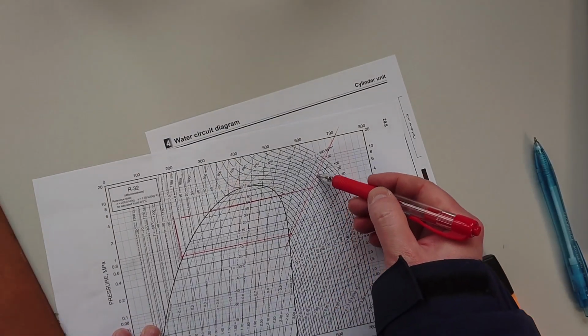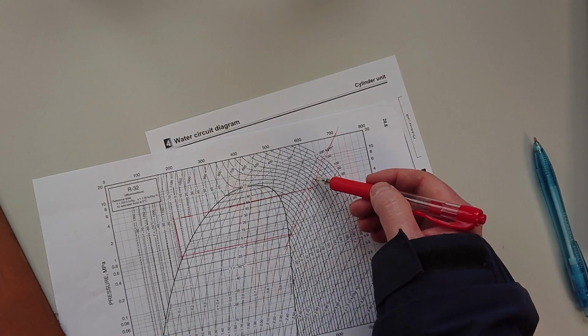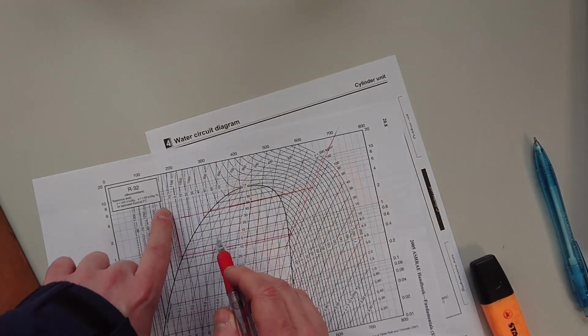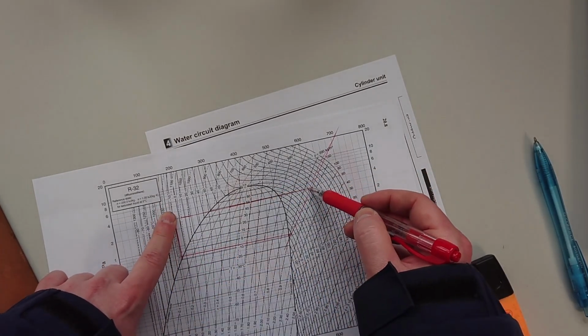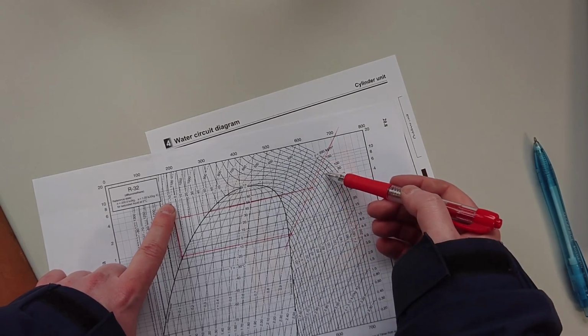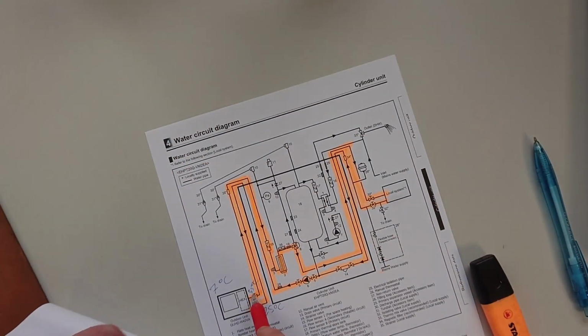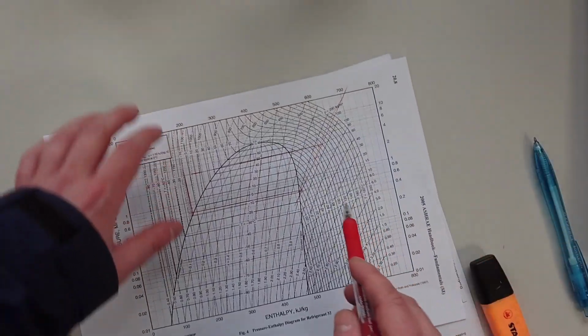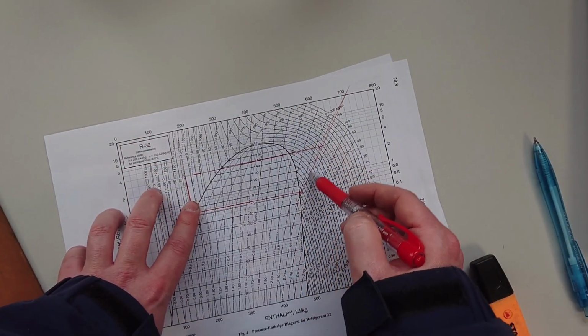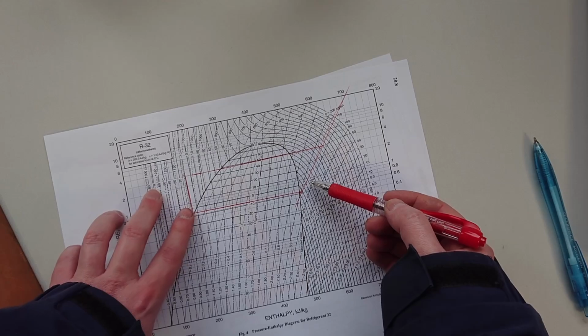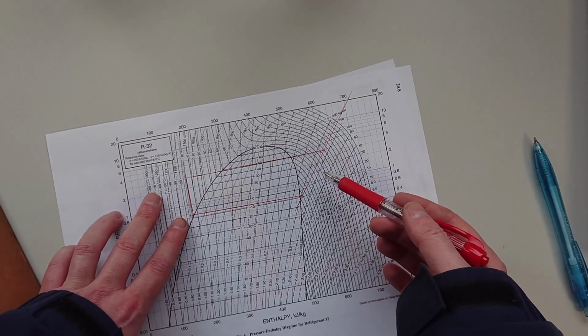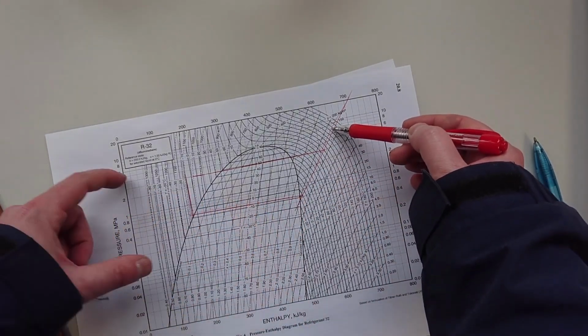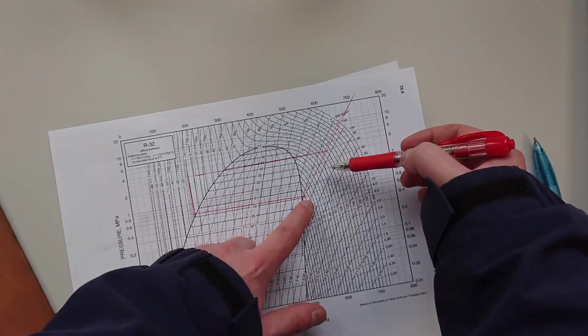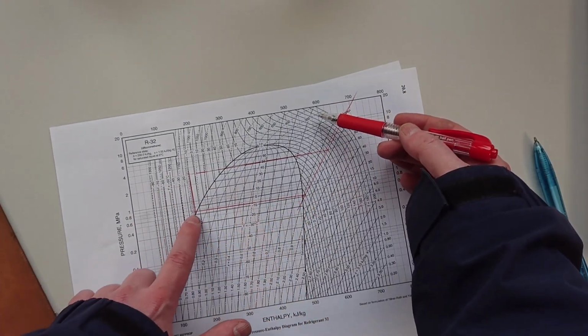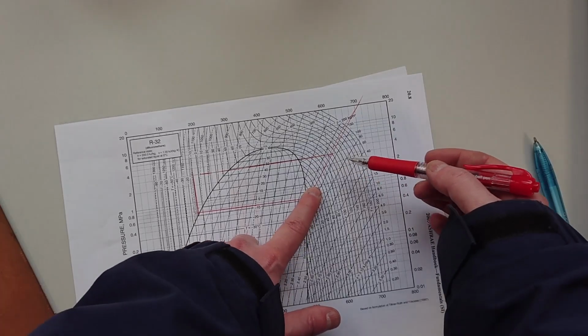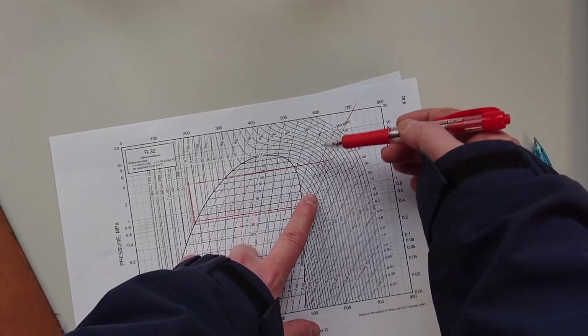But then what happens, as we come up on this line here, because they're not perfect and not ideal, this bit here is fixed because this is your outside temperature. And then we come up and up and up here to raise the water temperature that you have coming out of your heat pump and therefore around your system. Well, what happens then is that we have to put in more and more energy, and refrigeration systems and heat pumps don't like pressure ratio. And the higher we go up here, the higher pressure we're at over here. So now we're increasing the pressure ratio, but this bit is fixed.